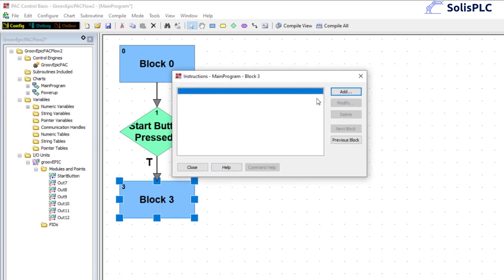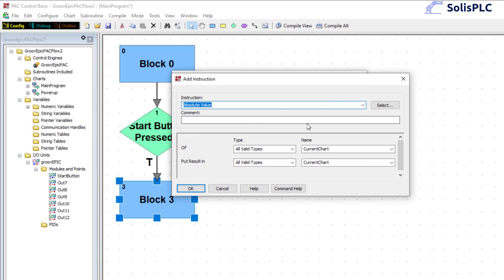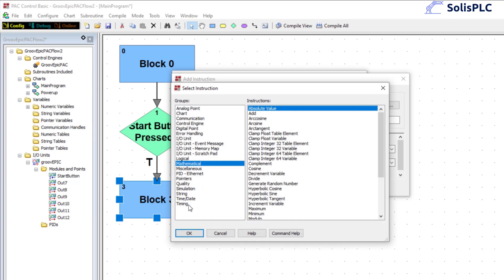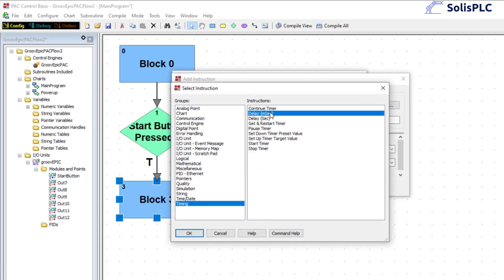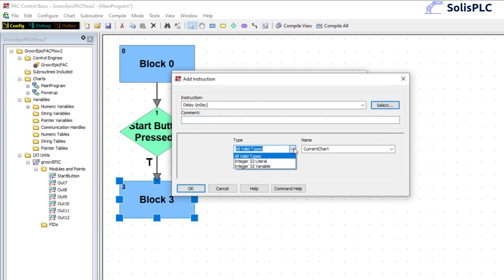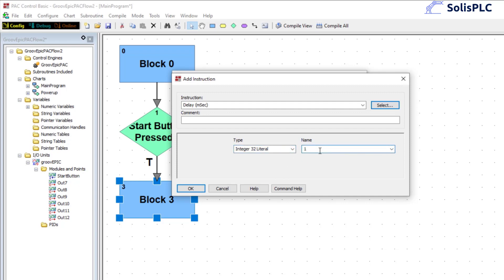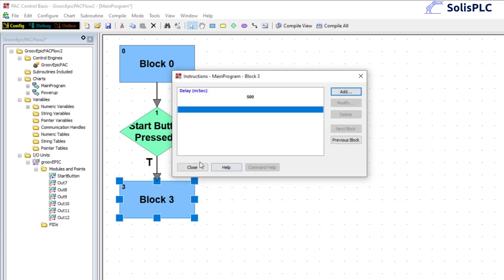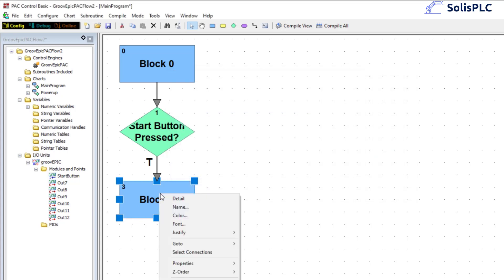This block is going to initiate our sequence. The sequence is: wait 100 milliseconds, turn on output 7, wait 100 milliseconds, turn it off — essentially toggling between outputs. Let's create the action: under Add, select Timing and do a millisecond delay, press OK. Instead of a variable we can set it to literal and type in 500 milliseconds — 500 just so we can see it a little better on camera. Press OK and close out of this interface.